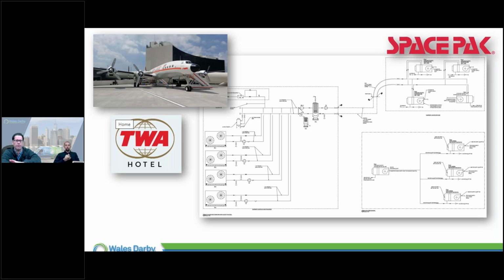Make sure you're only using the glycol required to maintain freeze protection, and be aware of what it says when it states -30 or whatever temperature you think you need to protect to. Don't over-glycol. You start to create more of a headache, and then your pump becomes a problem, not transferring heat or cooling. The glycol also needs to be maintained. It only has a shelf life of X, so you test it and recharge it if you have to.